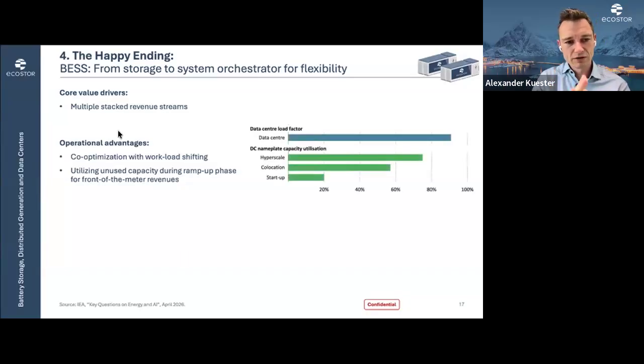There's a really good IEA report called Key Questions on Energy and AI. It backs up the claim that even the most efficient hyperscale data centers are only using roughly 75% of their nameplate grid capacity. For a classic co-location data center, it's even less—around 55%. And if that data center is still in the ramp-up or startup phase, it's even closer to 20%.